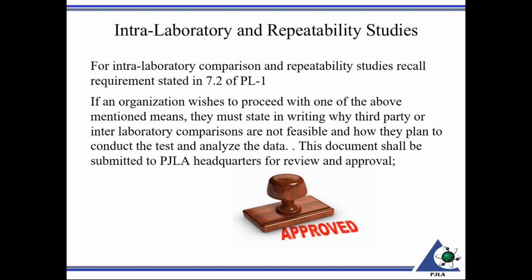I'll give you a couple examples. Say you're calibrating pipettes. There's no way we will approve that as an intra-lab or repeatability study, because if we are aware of a third-party provider out there that you can use, we would require you to either A, use that third-party provider, or B, conduct an interlab test. And it's something that I sincerely hope that we are consistent with at PJLA. It wouldn't be fair, for example, if you're calibrating pipettes and we require one organization to either use that third party or interlab, and have another organization get approved for intra-lab. So that's the main reason for being consistent on that. And if there is a third-party provider, if we're aware of that, we would require you to use it.